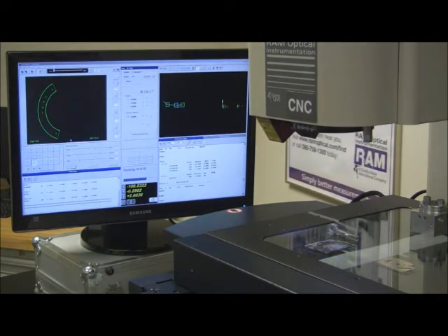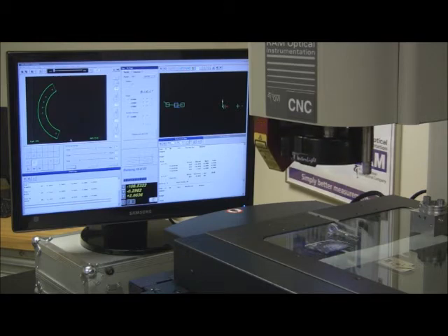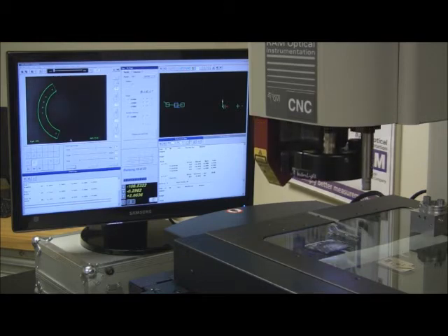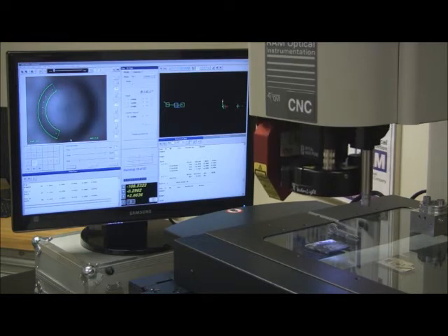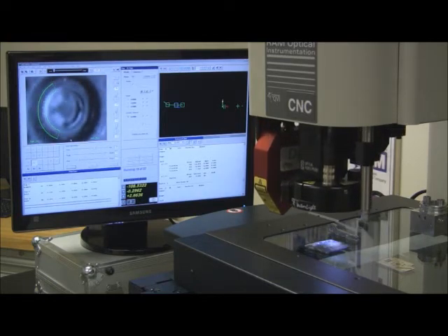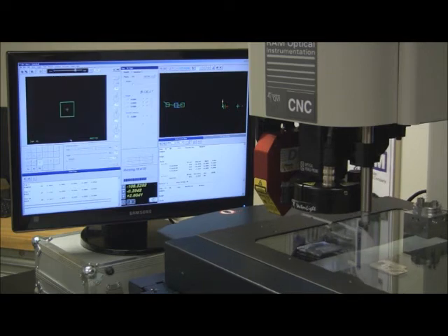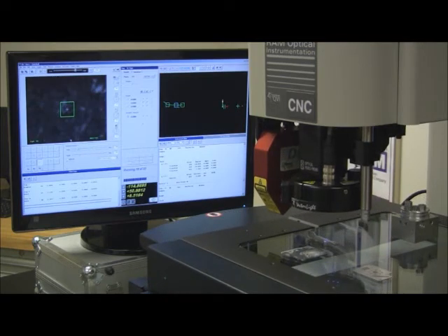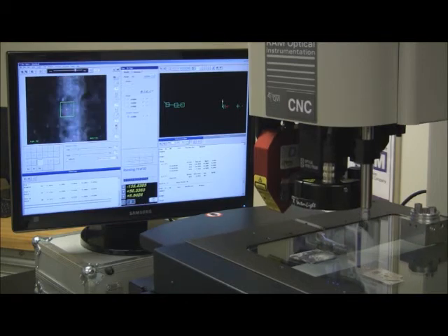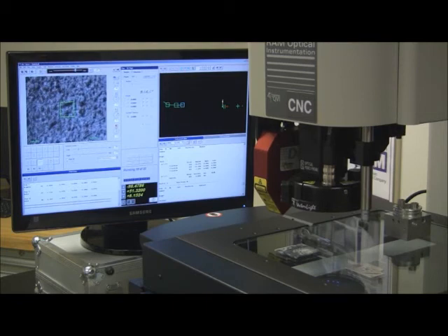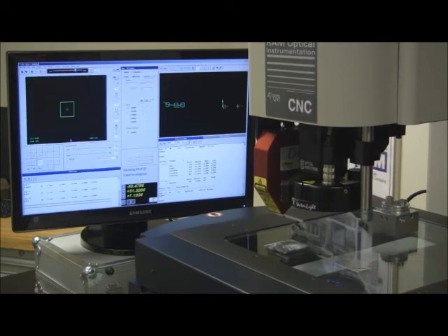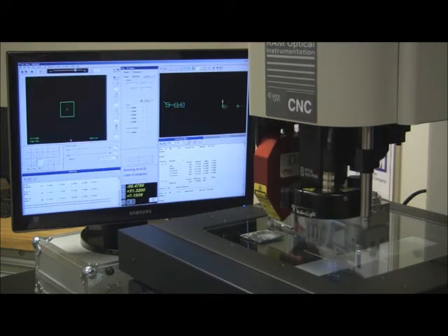We deployed the laser, and after we deployed the laser, we came down and scanned the part. Again, the laser has the ability to measure points for z-axis focus. You can measure a plane using lines to create the plane. We can do a circular scan if we want to measure the top of a bottle. I'm focusing with the laser right now. And again, the laser focus is much faster and certainly more accurate than the video focus. Now we're actually scanning the part.